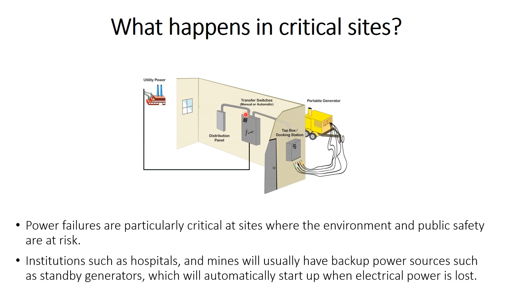So at the beginning, in normal operation, the utility power provides power to the distribution panel by using this switch. This switch is taking the electrical power from the utility power to this distribution panel, which provides power to the hospital, for example. Now, in case of a fault on the utility power, what does this automatic transfer switch do? It transfers the power from the utility power grid to a portable generator. So we take electrical power from the generator to the distribution panel. That is the benefit of the ATS or automatic transfer switch, which is usually automatic, and sometimes it can be a manual switch.